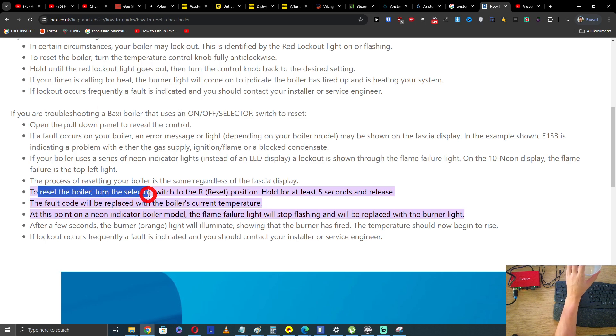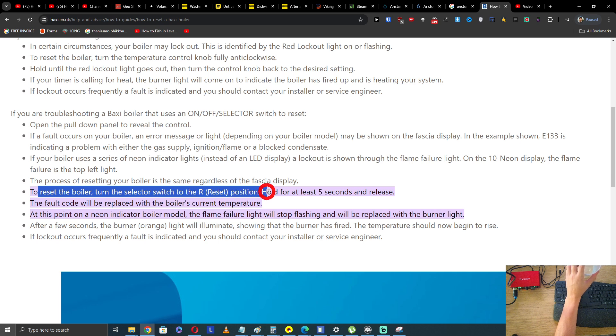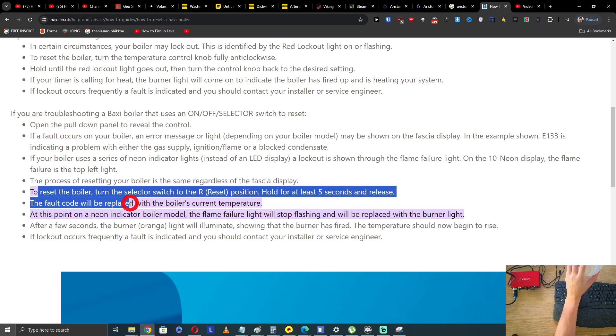To reset the boiler, turn the selector switch to the R (reset) position and hold for at least 5 seconds and release.